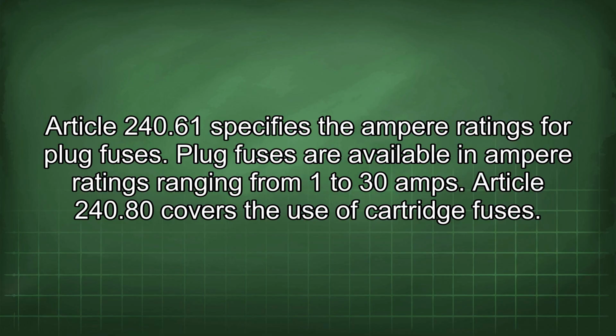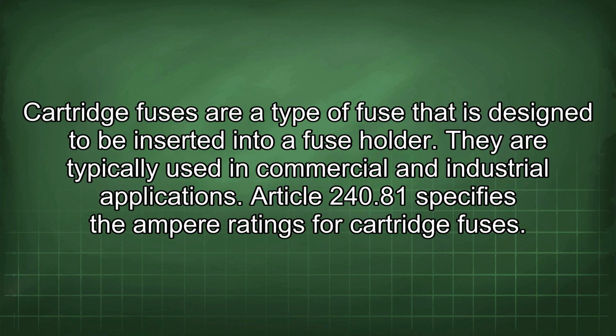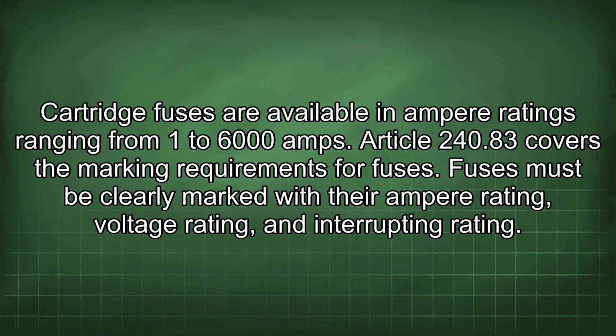Article 240.80 covers the use of cartridge fuses. Cartridge fuses are a type of fuse that is designed to be inserted into a fuse holder. They are typically used in commercial and industrial applications. Article 240.81 specifies the ampere ratings for cartridge fuses. Cartridge fuses are available in ampere ratings ranging from 1 to 6,000 amps. Article 240.83 covers the marking requirements for fuses. Fuses must be clearly marked with their ampere rating, voltage rating, and interrupting rating.